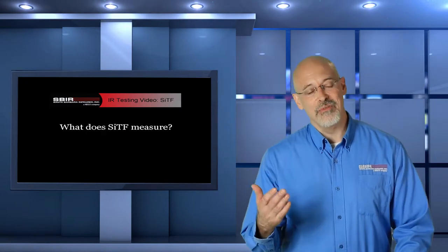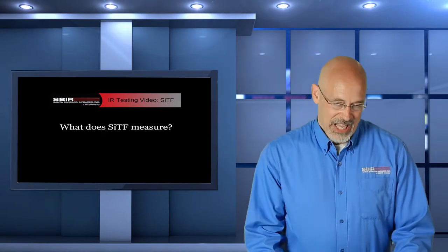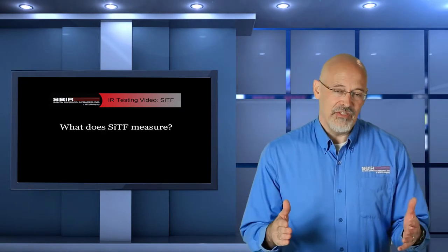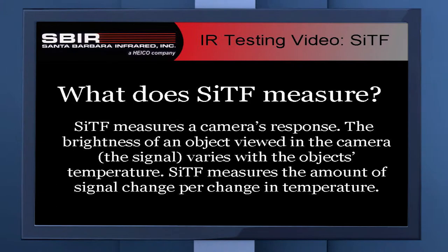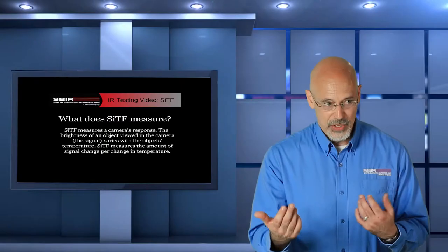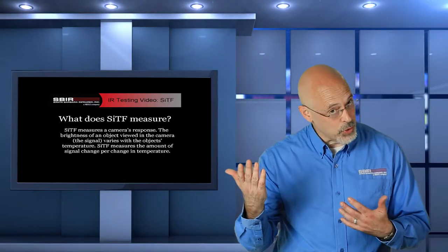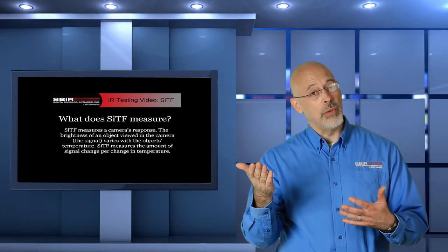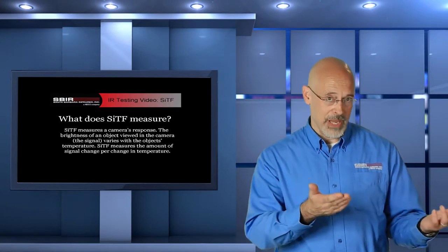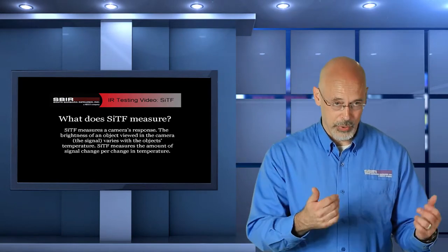So what does SiTF measure? SiTF measures the response of a camera. It looks at the brightness of the output signal based on how much temperature is being presented to it, the input signal. So that's pretty much what we're measuring: the amount of signal output based on the amount of temperature input.